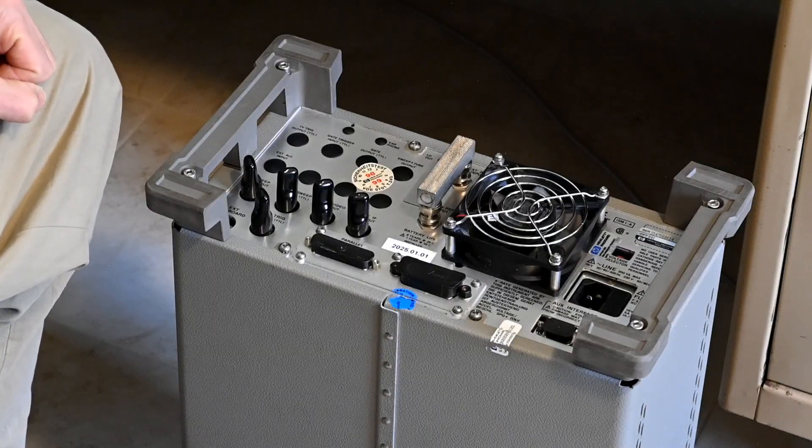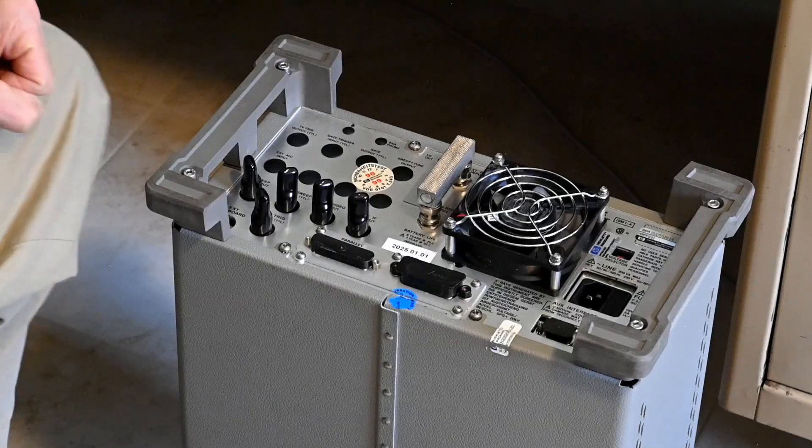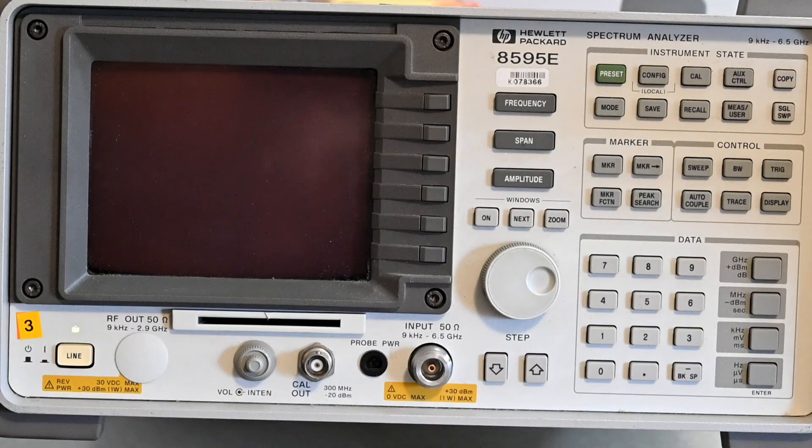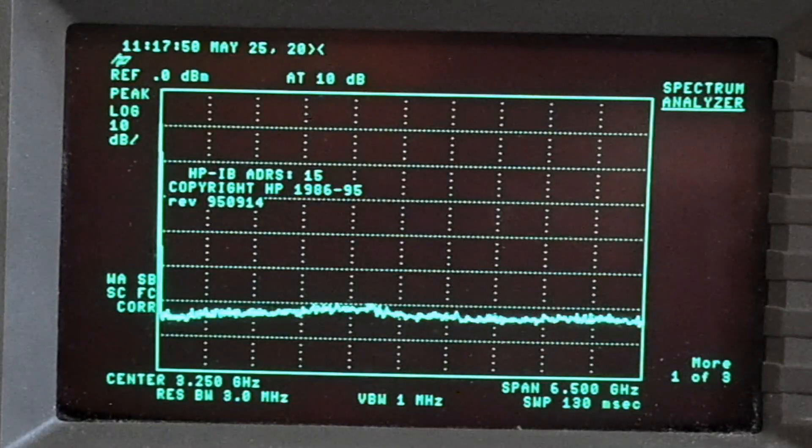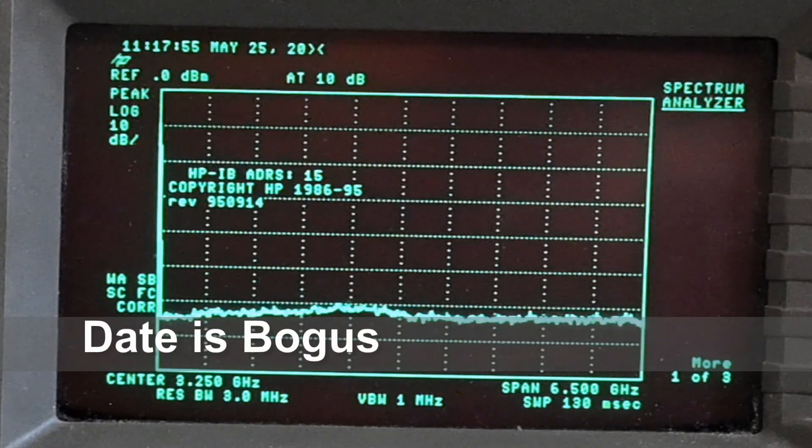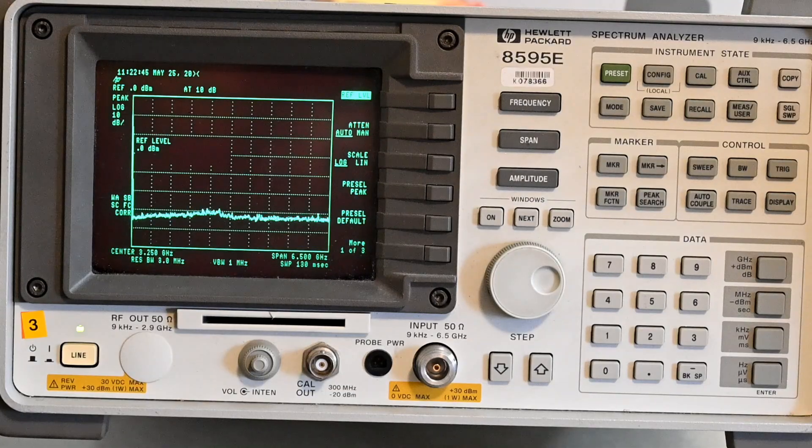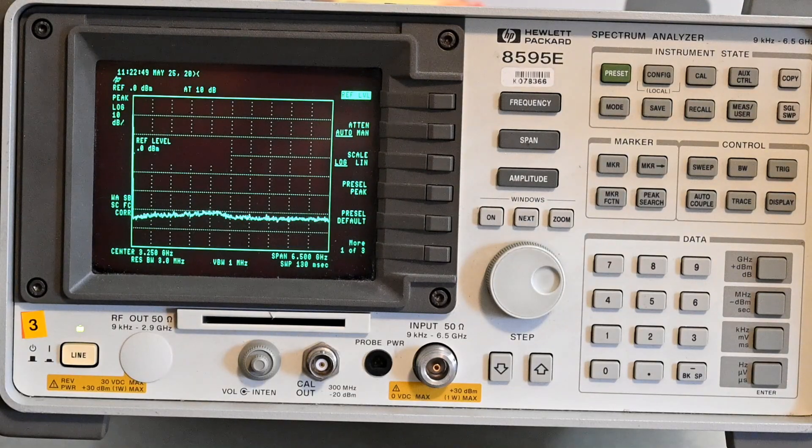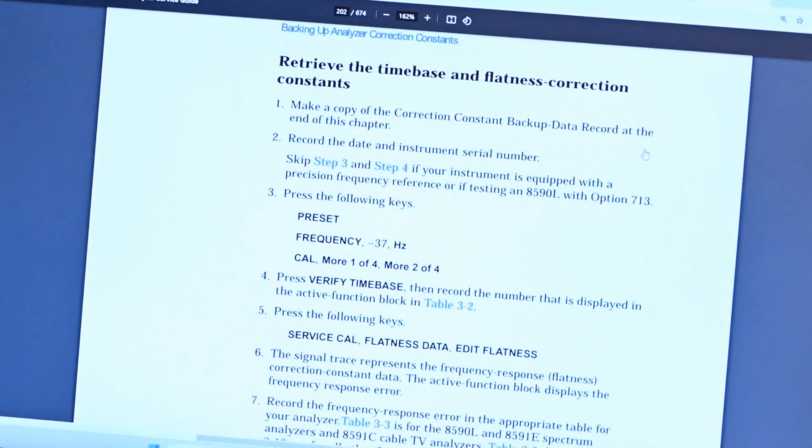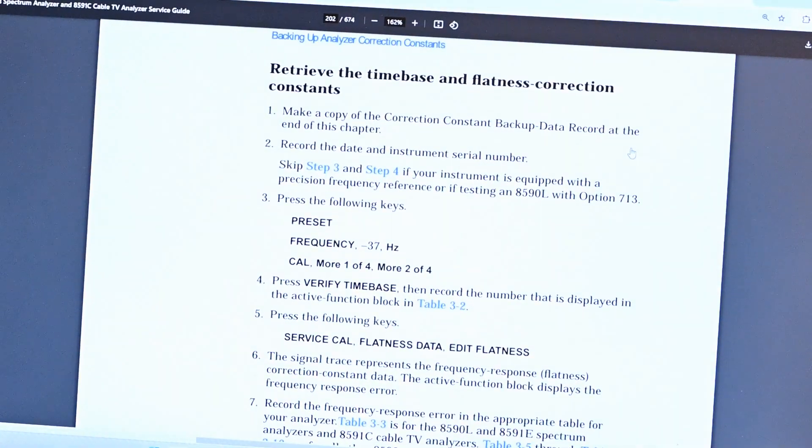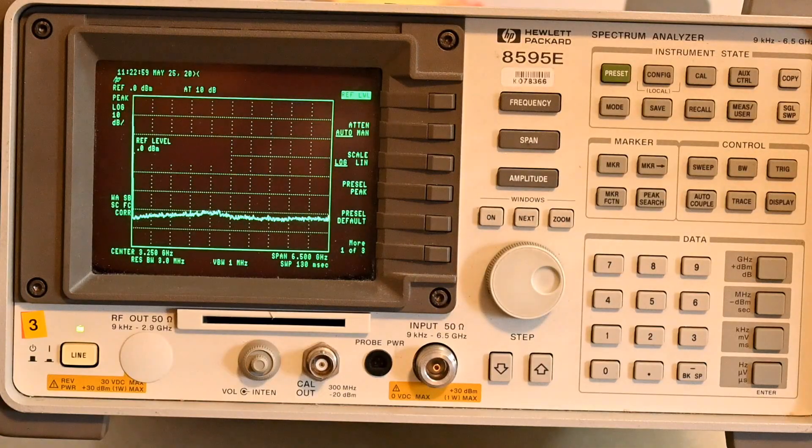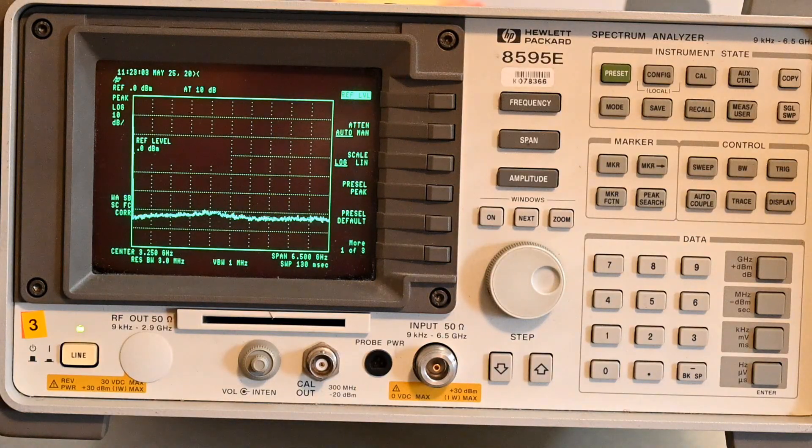Let's power up the unit and make sure that the calibration data is still in there and then we'll be set to go. The time I'm noticing is more or less correct, May 25th. I'm not sure why it's not giving me the full date there. Now we're going to check the calibration constants, which we've previously written down on a piece of paper. This is from the service manual for the 8590 Spectrum Analyzer, so you just need to go in there and it'll give you complete instructions starting from page 202.